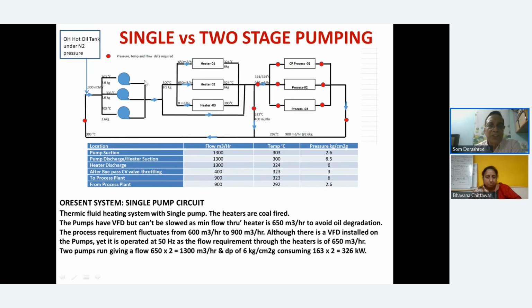Each of these pumps is about 650 meter cube per hour. Now the requirement is, these are all coal-fired heaters, so for each one of them you cannot reduce flow below 650. Otherwise the oil will get degraded because the temperatures are bound to go higher. So they have a VFD on all of these. I don't know for what reason, but the VFD is running at full 50 hertz. So the first thing we asked them is that the VFD does not come free. So simply bypass it straight away and start saving something, because you're not controlling. You have to maintain 650 here.